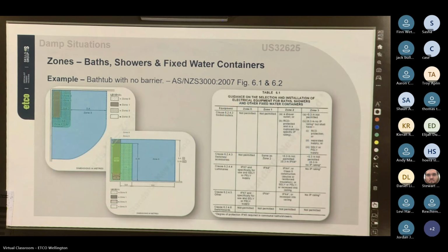So to really understand how zones work, we'll look at one particular example straight out of AS/NZS 3000. It shows us the dimensions of the zones around a bath or shower, so you can actually see the zone. Once we've got the visual in our head, table 6.1 will tell us the types of fittings and equipment allowed in each zone. So you'll see in zone 0, it's very restrictive, while zone 2 gives us more options. After we've looked at that, we'll look at some other common bathroom layouts: showers without trays, basins, corner baths, etc. So we can see how the zones change depending on the situation. This way, you won't just memorize the numbers, you'll be able to apply them to any bathroom you come across.